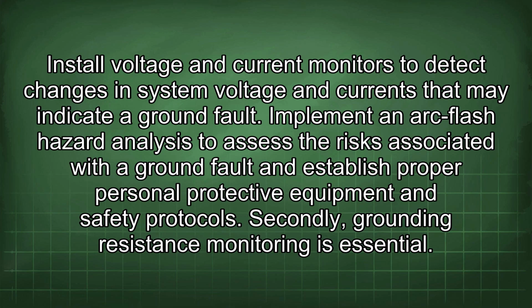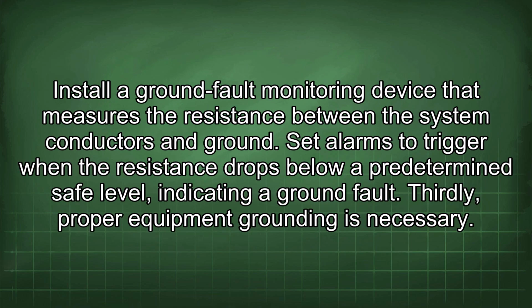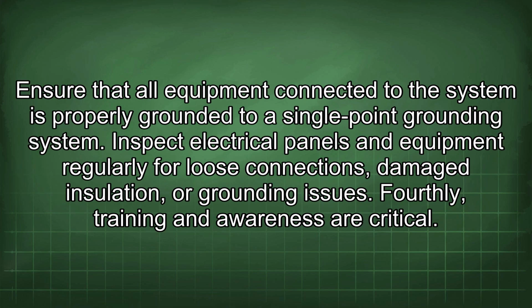equipment and safety protocols. Secondly, grounding resistance monitoring is essential. Install a ground fault monitoring device that measures the resistance between the system conductors and ground. Set alarms to trigger when the resistance drops below a predetermined safe level, indicating a ground fault. Thirdly, proper equipment grounding is necessary. Ensure that all equipment connected to the system is properly grounded to a single-point grounding system. Inspect electrical panels and equipment regularly for loose connections, damaged insulation, or grounding issues.